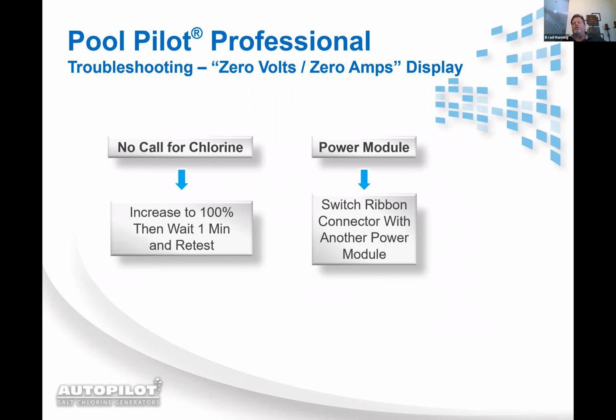It doesn't have a boost button, but if you go into the programming, you can go into the installer menu and turn the boost mode on, and you can set the hours of how long you want the boost cycle to run. But anytime you walk up and do a test, the cell has to be energized. All right, you've got 0 volts and 0 amps with the system energized or the cell energized.